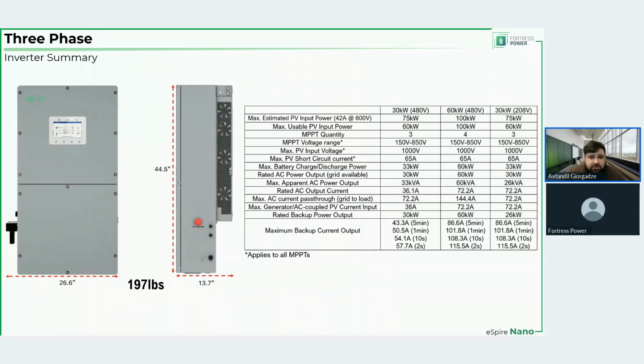Maximum battery charge and discharge power for 30 kilowatt inverters is 33 kilowatts, not 30 kilowatts. And for the 60 kilowatt inverter, it is 60 kilowatts. The rated AC output when the grid is available is 30 kilowatts for the 480 volt 30 kilowatt unit, 30 kilowatts for the 208 unit, and 60 kilowatts for the 60 kilowatt 480 volt unit. But as I was saying before, the backup power that the 30 kilowatt 208 unit has available is slightly less than its AC rating. So it's 26 kVA of backup power. Currents you can see here for yourself.